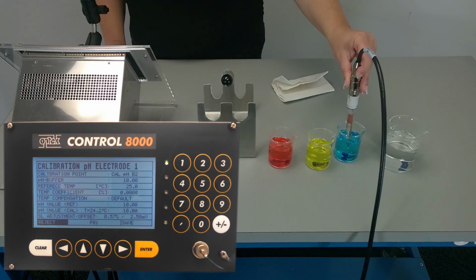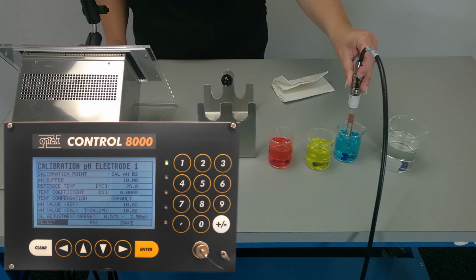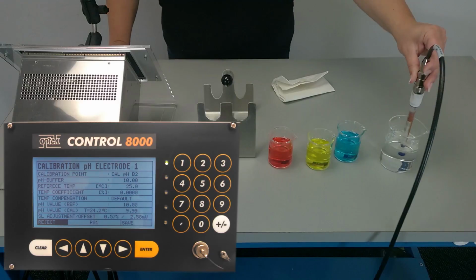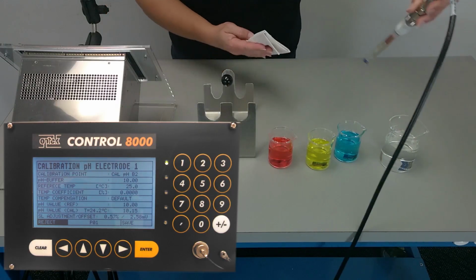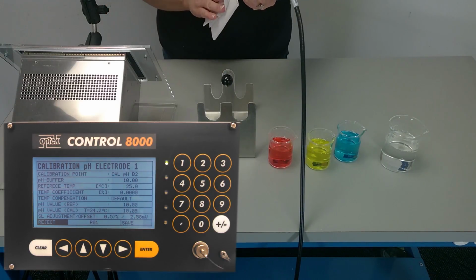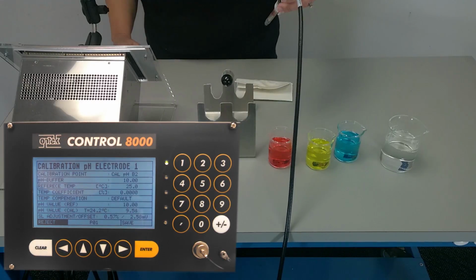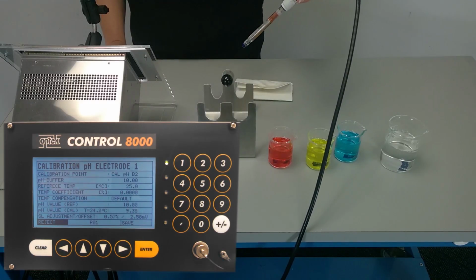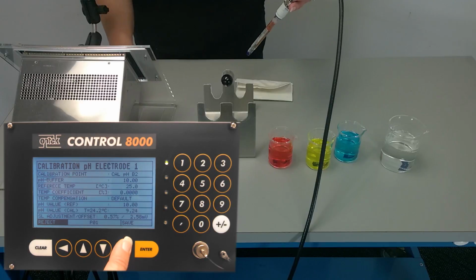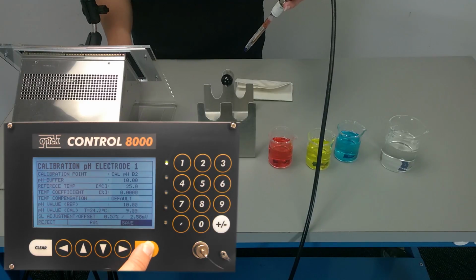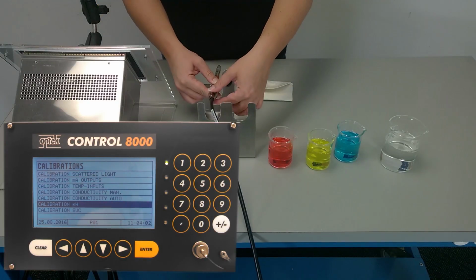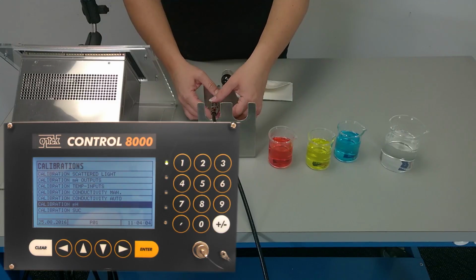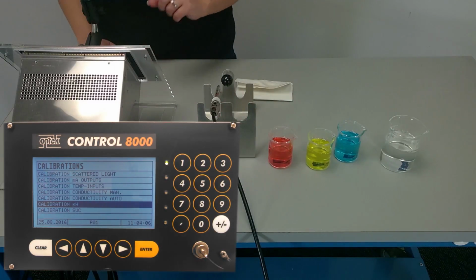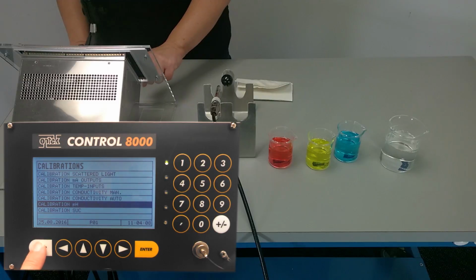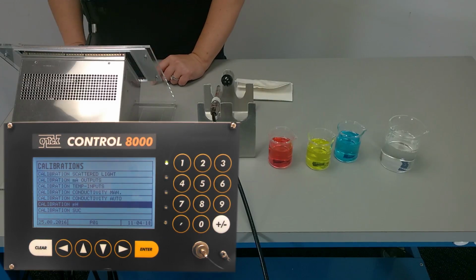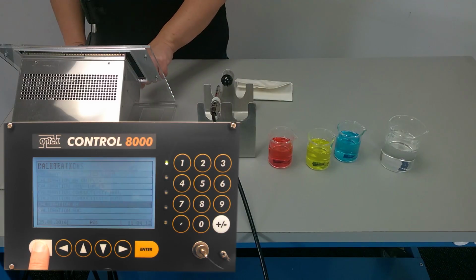And at this time, the converter will show a slope and offset calculation. This will be the only time that you will see this calculation during the calibration process. So if it's needed for any documentation, this will be the time to record it. Once that is done, scroll over to Save. And then we are going to update our calibration setting in the converter, and then we will check a buffer 7 for a verification. So from the calibrations menu, you're going to hit clear twice.